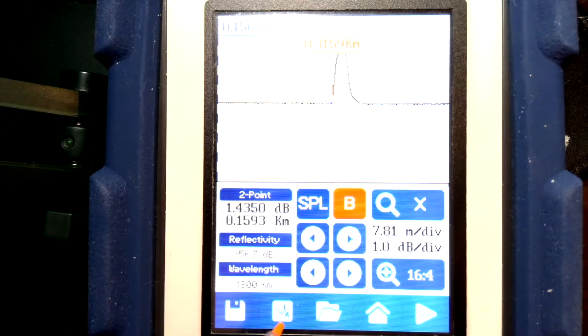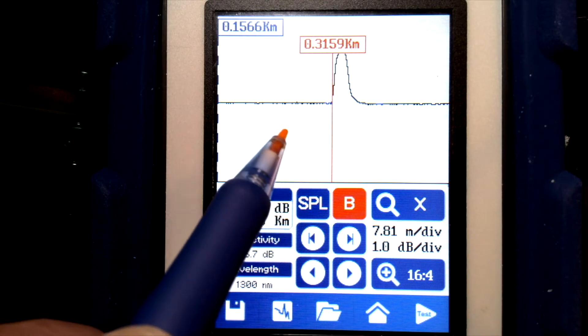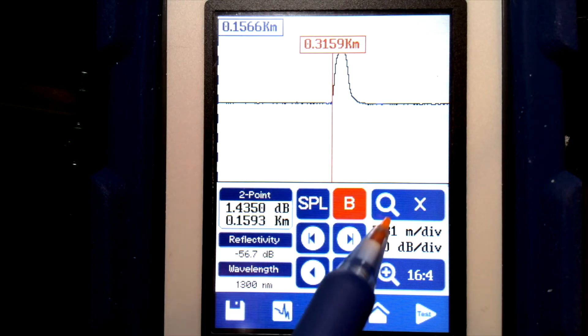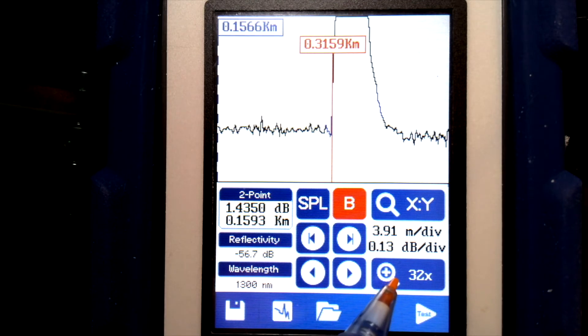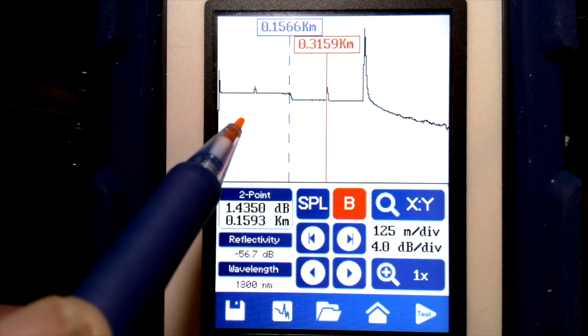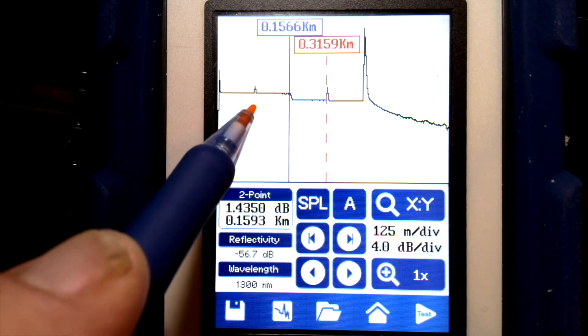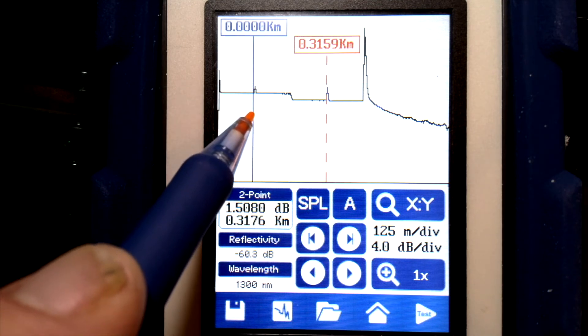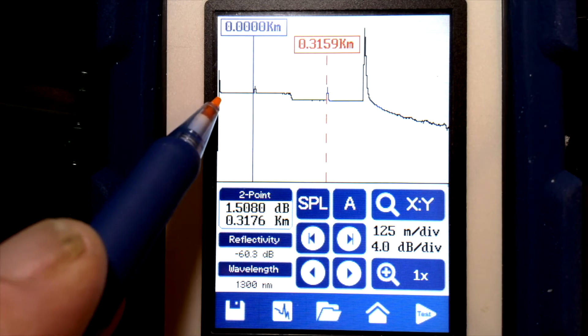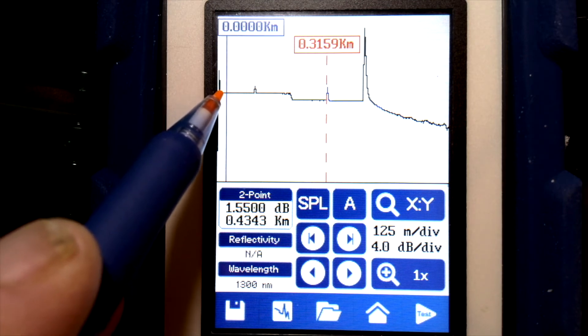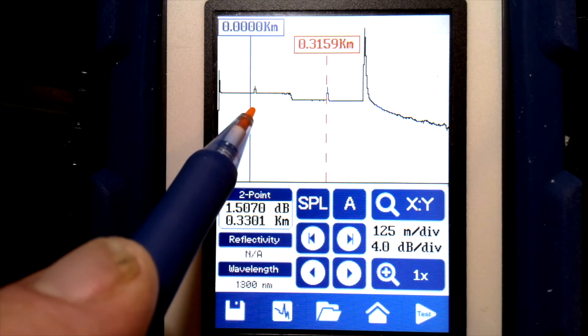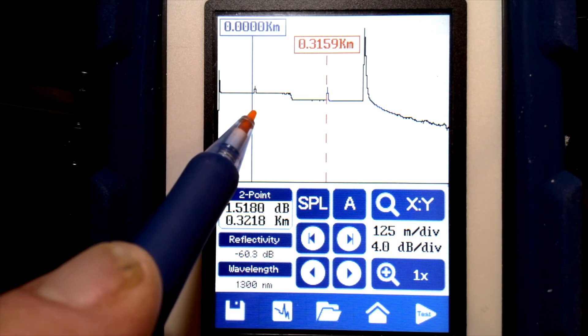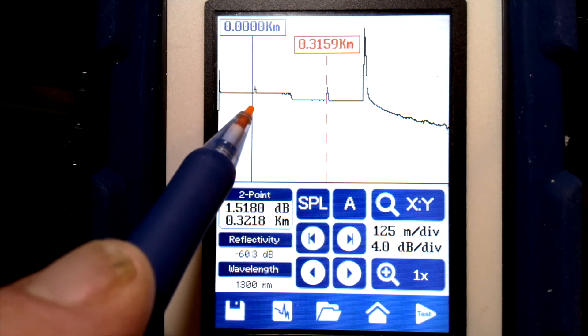Pushing this button here will let us see the trace view. I'm currently zoomed in because it remembers my zoom settings from previous testing, so we'll zoom it back out. Here's a view of our whole trace. I'll go ahead and choose my A cursor and place it at the first event — it's showing 0 meters here rather than at the start because I had a launch cable selected. It's ignoring the first 150 meters and treating this first connector as the start of the fiber, letting me measure this first connection and ignore the launch cable length and loss.